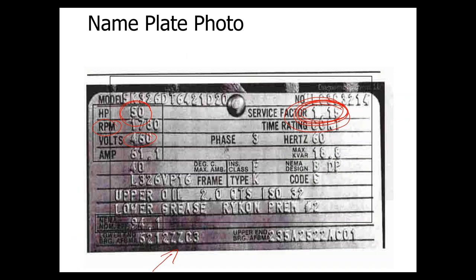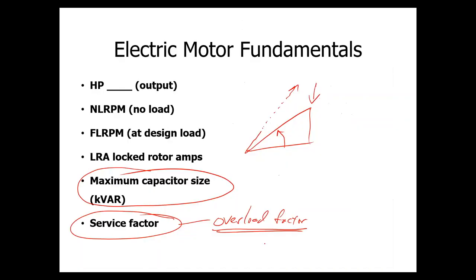Different manufacturers have different lengths of time you can do that, but most of them would say you can run it indefinitely 15% overloaded. If you go beyond that, you're going to heat up the motor and burn out the windings and then have a burned out motor.